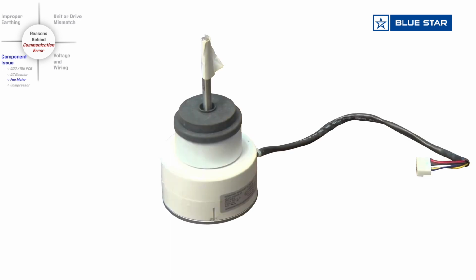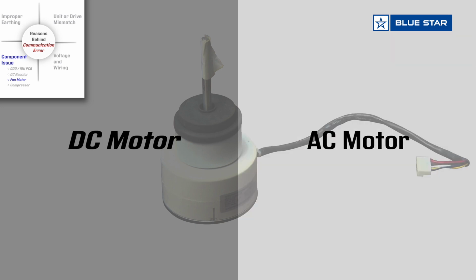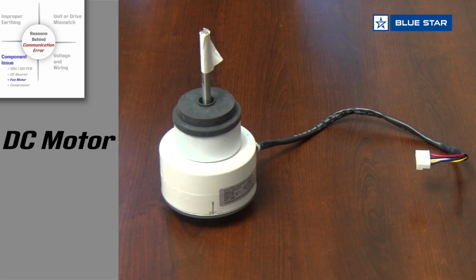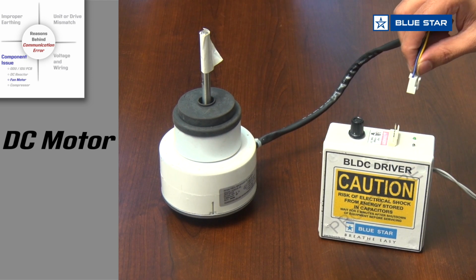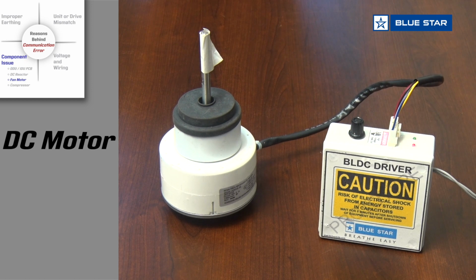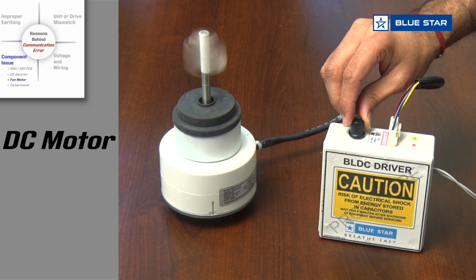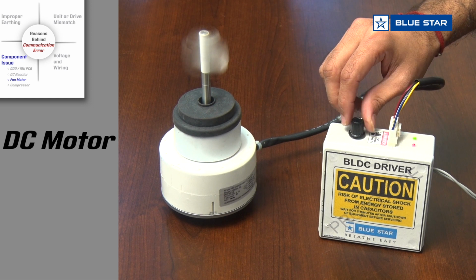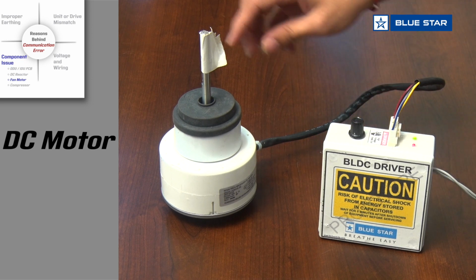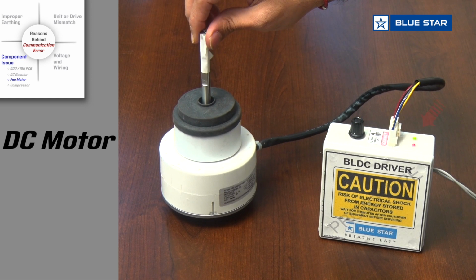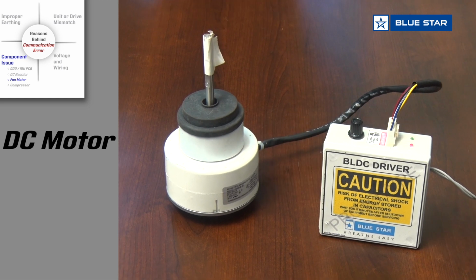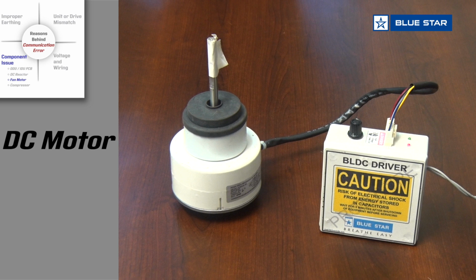Depending on the model, the unit has either DC motor or AC motor. In case of DC motor, use the BLDC kit to check the motor. Connect the motor to the BLDC kit and rotate the regulator. If the motor is in a healthy condition, it rotates on moving the regulator. At standstill, if we rotate the motor shaft manually, the LED blinks on the BLDC kit. If the motor is faulty, then it will neither rotate on rotating the regulator on the kit, nor the LED on the kit blinks on rotating the motor shaft manually. In such a scenario, we can conclude that the motor is faulty and has to be replaced.